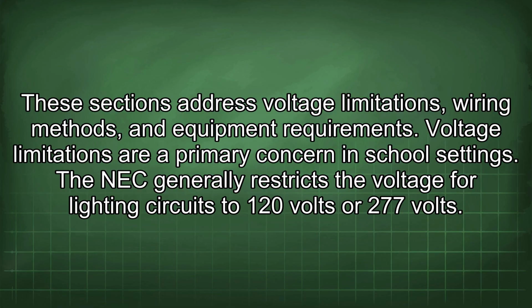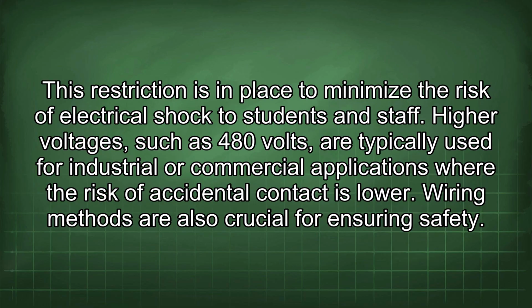The NEC generally restricts the voltage for lighting circuits to 120 volts or 277 volts. This restriction is in place to minimize the risk of electrical shock to students and staff. Higher voltages, such as 480 volts, are typically used for industrial or commercial applications where the risk of accidental contact is lower. Wiring methods are also crucial for ensuring safety.